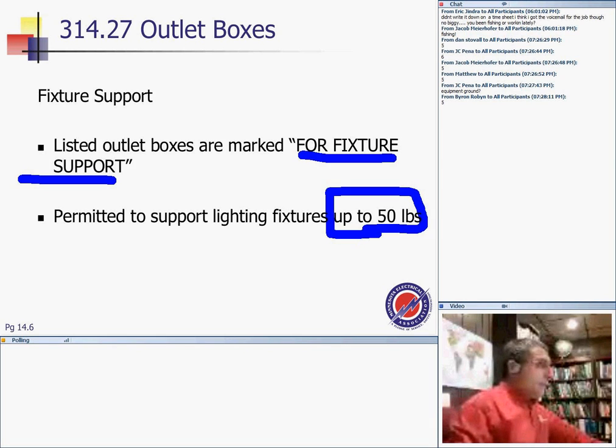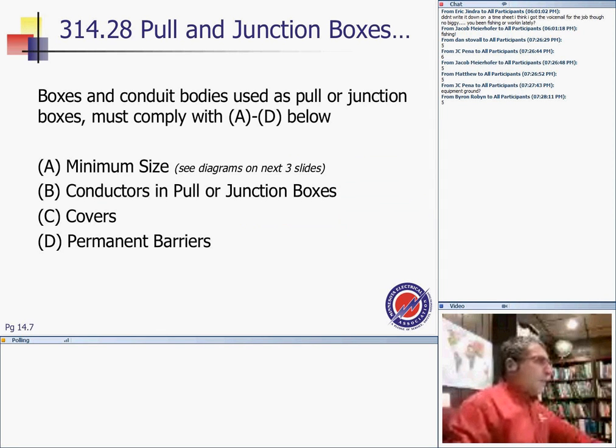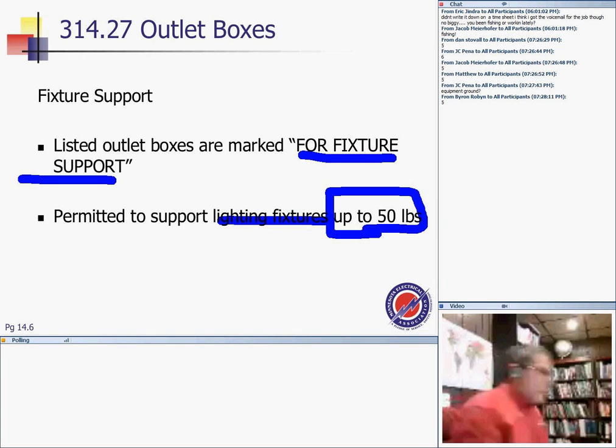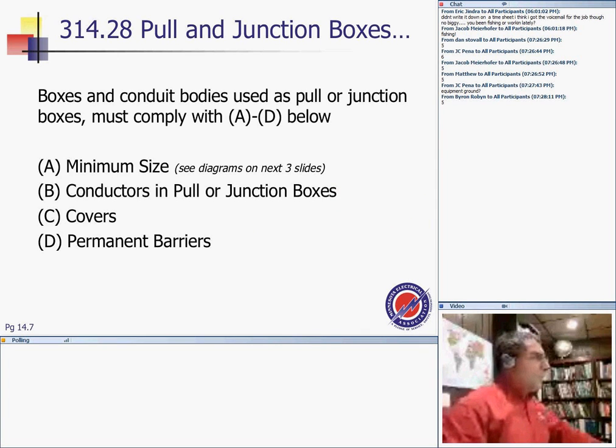a listing, and it can support up to 50 pounds. Don't get confused between this one and 35 for fans, guys. For 35, the fan box has to support 35. If it's rated for 35, it has to be labeled, and you cannot support any fan more than 70 pounds. At 70, you have to hire your structural engineer after that. So basically, in terms of box support, before we move into the pull and junction boxes, any questions?